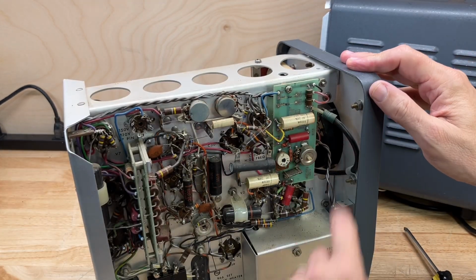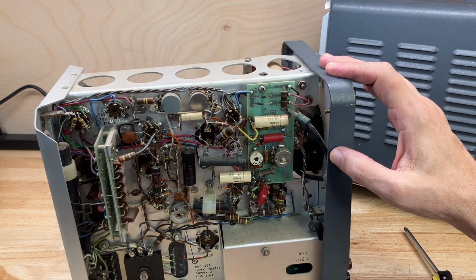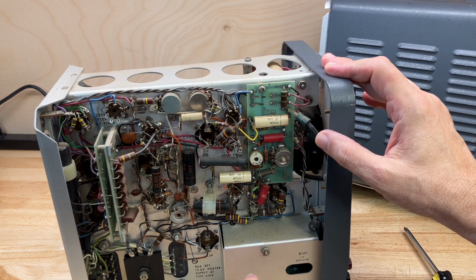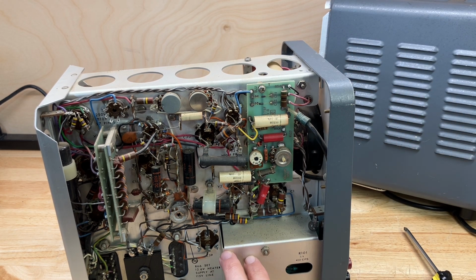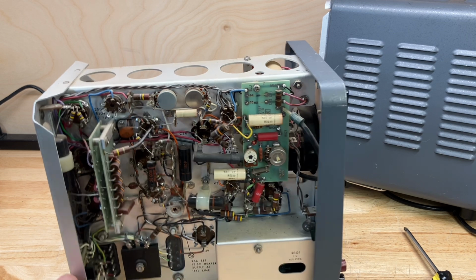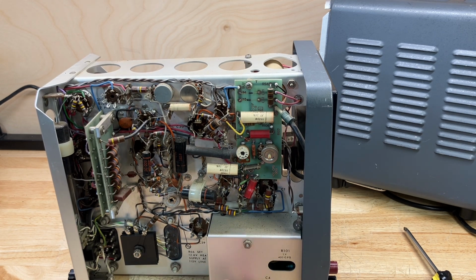But I'm going to have to pull this meter movement out and try to figure out why it is sticking. Now, I do have an operating and service manual on order for this thing, but it hasn't come in yet, so I guess we're going to have to wait for that to maybe finish the repair on this instrument. I'm sure that'll be here in a couple of days, then I can finish up this video. In the meantime, I'll just take an air hose and blow out the dust, and maybe a paintbrush or something, and scrub it a little bit. See if I can pull this meter movement out and open it up and figure out why the needle is sticking, because it's in the meter itself, not in the electronics of the instrument. It seems like all of the electronics are working.